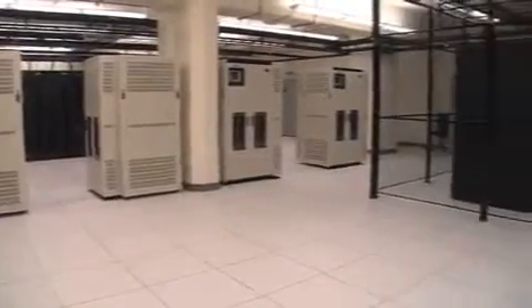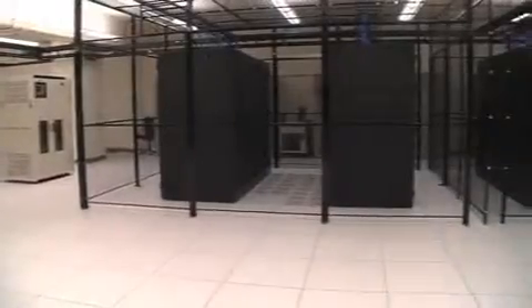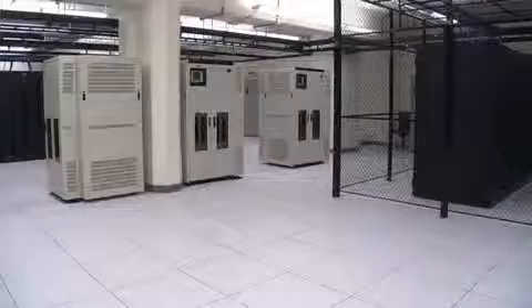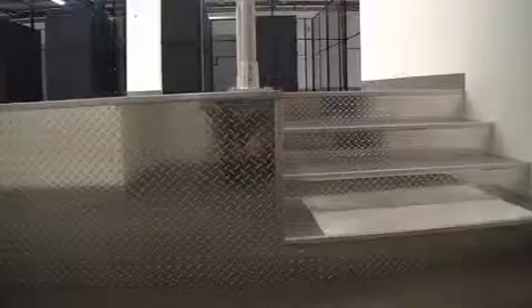So the data center is state-of-the-art and is designed to support mission-critical applications. We have a number of measures in place to make sure that everything's completely redundant and secure. So first of all, we have 30-ton CRAC units around the perimeter of the facility to facilitate cooling. This facility can handle 200 watts per square foot of cooling capacity, and we can flex beyond that to 400 watts a square foot. You can see from the massive columns that the structural loading in this building is off the charts. There's no water overhead. It's got a poured concrete roof. There's fire and smoke detectors in the ceiling and also underneath the raised floor.